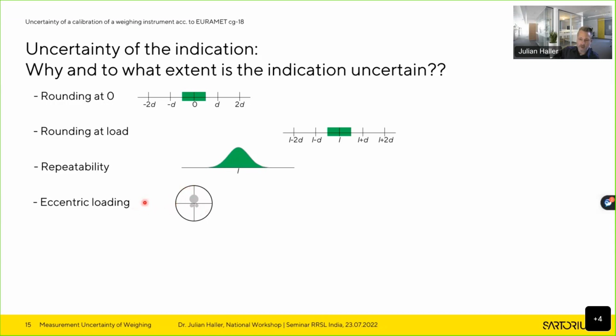And that's why you have to consider eccentricity of the weighing instrument as an uncertainty contribution. And again, this is why in a calibration of a weighing instrument, you have to measure the eccentricity to find out, for this particular weighing instrument, how large this effect will be.